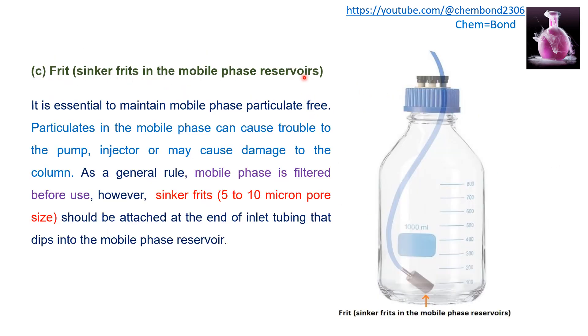The frit or sinker frits in the mobile phase reservoir are essential to maintain the mobile phase particulate-free. Particulates in the mobile phase, if present, may cause trouble to the pump and injector, and may cause damage to the column. As a general rule, the mobile phase should be filtered before use to remove any particulates. Sinker frits with a pore size of 5 to 10 microns should be attached at the inlet of the tubing that dips in the mobile phase reservoir.